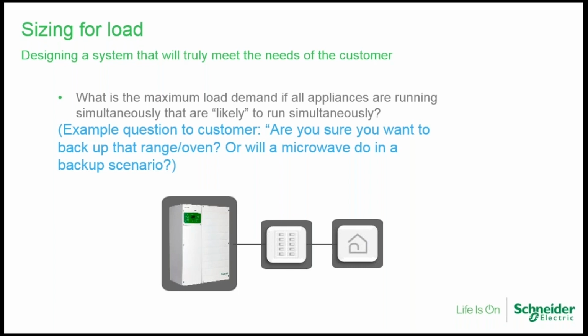Make sure the customer understands that higher demand, such as air conditioner, electric range, will require a larger system. So you might want to have a conversation. Are you sure you want to back up that range or that electric dryer? In other words, will a microwave do in an outage? Or could you get away with maybe hanging your clothes up? If the outage is rare and of short duration, they might be willing to do that. Otherwise, they're going to have to size the system up, and that's going to be more expensive.